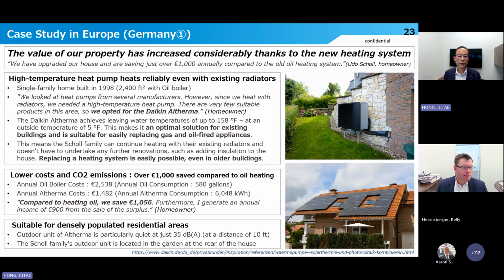Let me point out 3 points on Daikin Altherma. First, the high temperature heat pump heats reliably even with existing radiators. They had been using an old boiler with radiators, so they needed a high temperature heat pump.